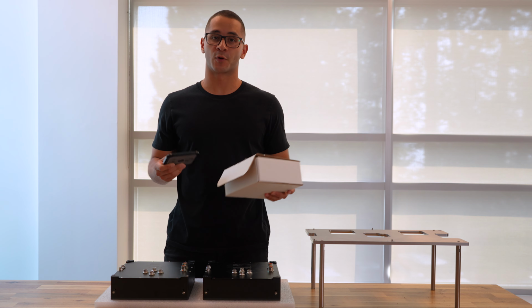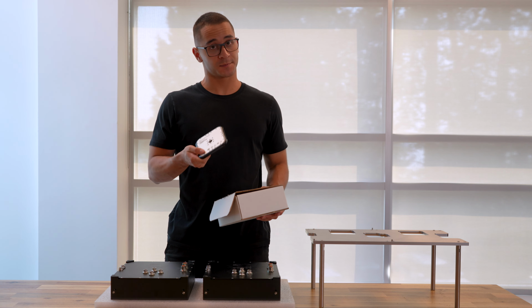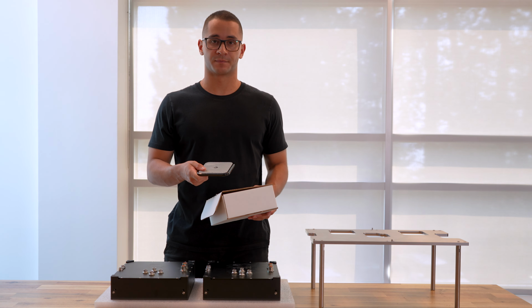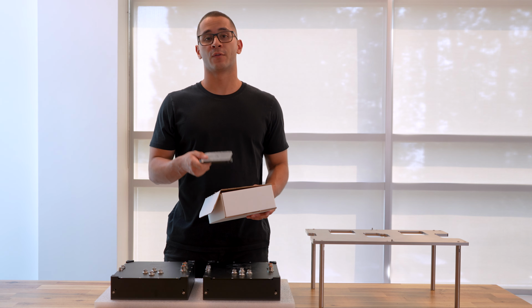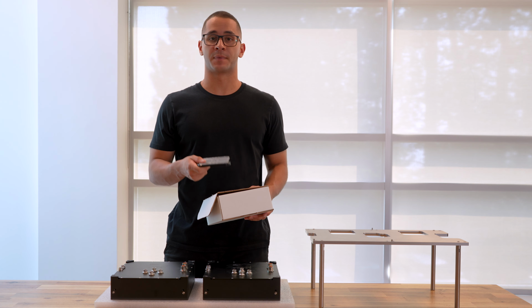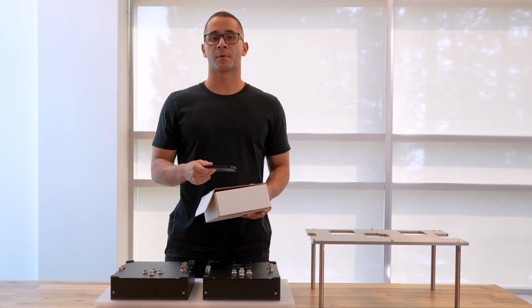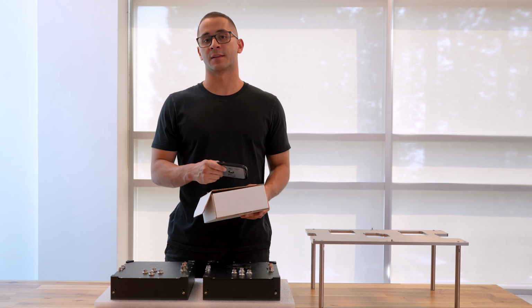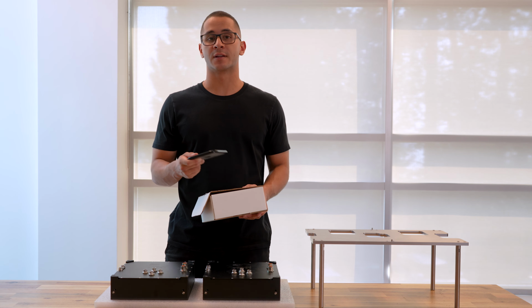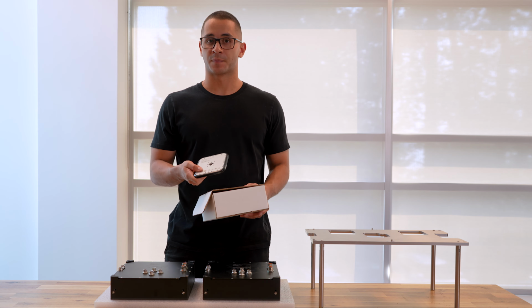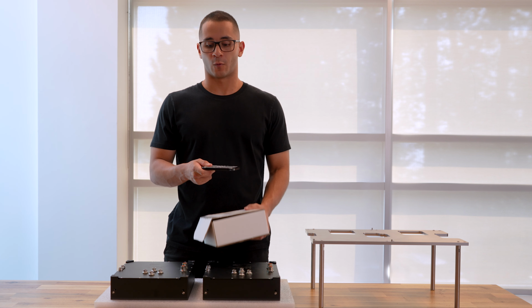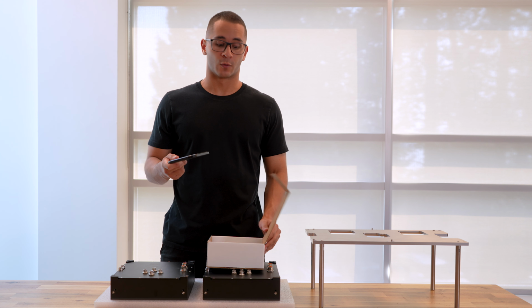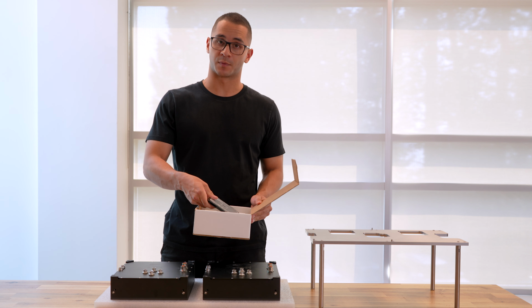First, let's have a word on safety. The X-spots have very strong magnets. You should be careful with ferromagnetic objects to prevent pinching hazards. People with active implanted medical devices should keep a distance of 20 centimeters between the X-spot and the implant. When the X-spots are not being used, we recommend you put them in the storage boxes provided.